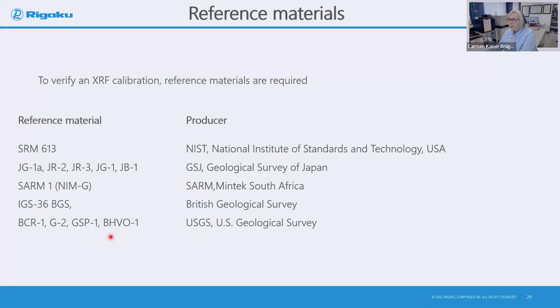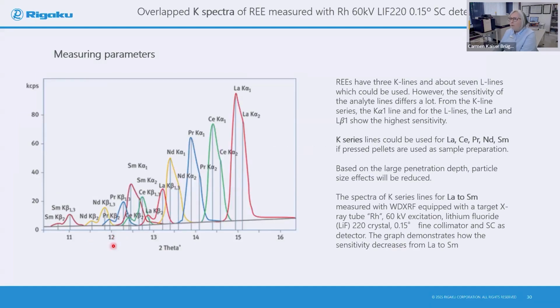So here you can see some examples of K-line spectra of the rare earths using the LiF220 with a 0.15 collimator and a scintillation detector. The rare earths have 3 K lines and about 7 different L lines, which can be used to develop our methods. However, the sensitivity of these lines differs a lot: from the K series, the K alpha line, and the L lines, the L alpha ones can show the highest sensitivity.